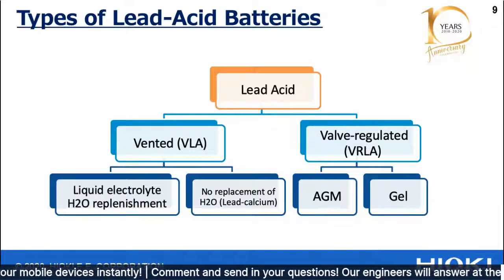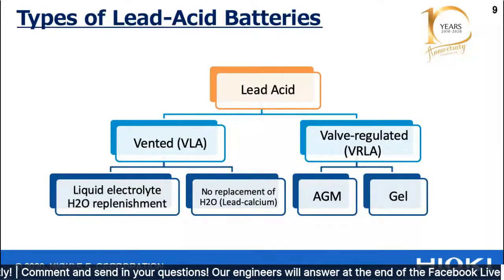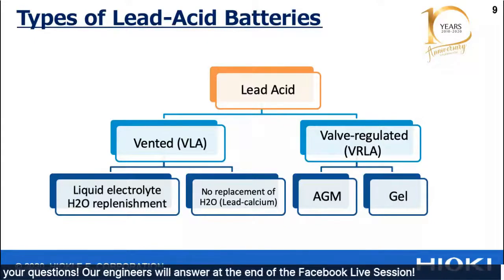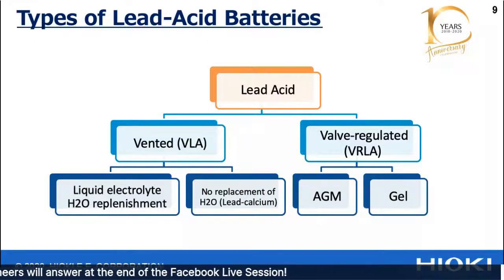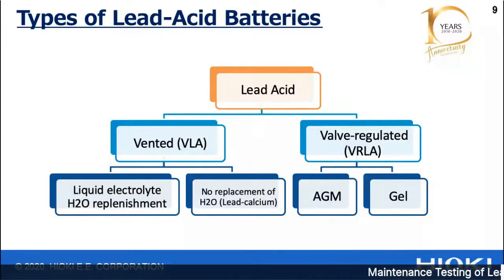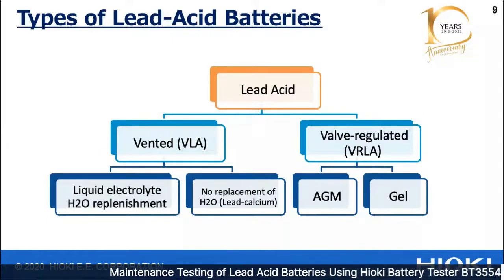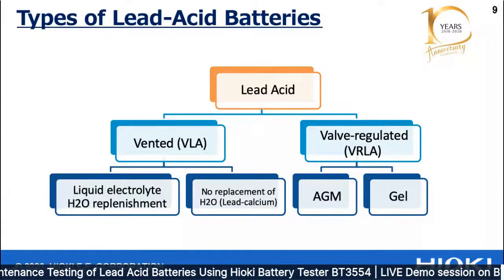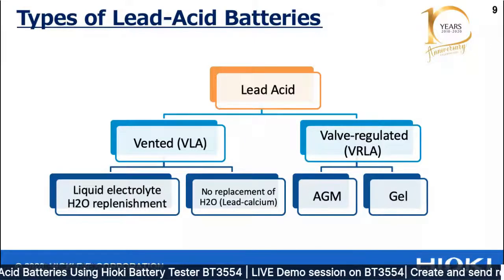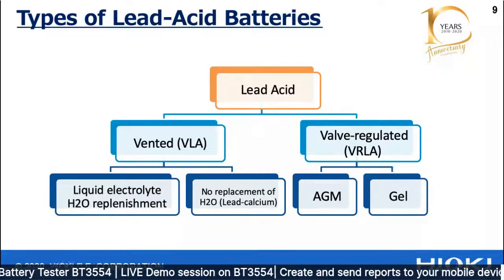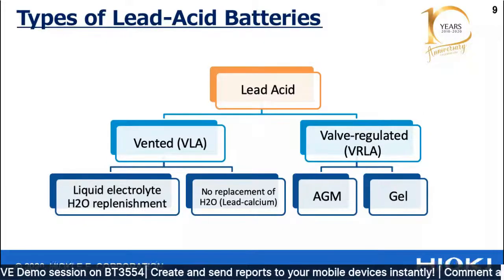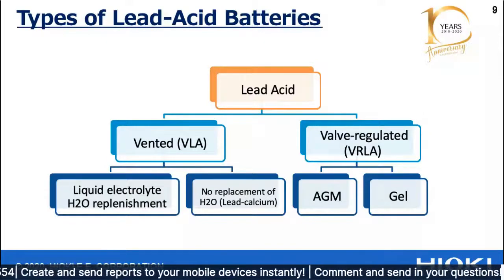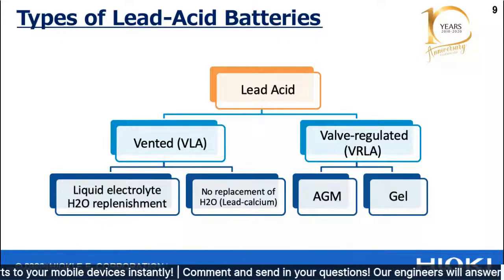Now, these types of batteries are usually installed on open racks in dedicated battery rooms that have a dedicated ventilation system. So you must have ventilation for such battery because it emits toxic gases. Now, there are two versions of VLA types. With the flooded batteries, lost water can be replenished by refilling with water. The second type does not need refilling due to the use of calcium plates to improve resistance to corrosion. So no excessive gassing, less water usage, and lower self-discharge for the second type of VLA batteries.